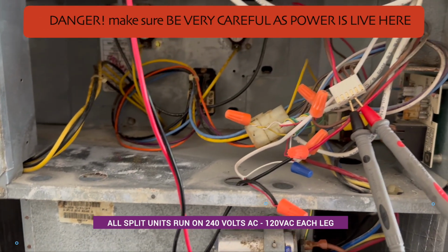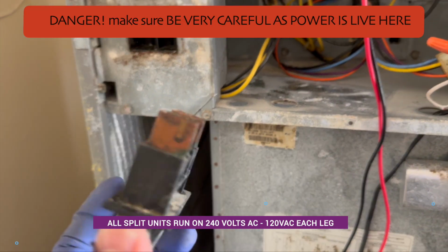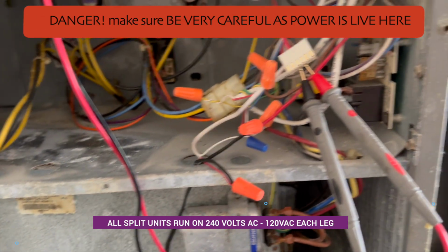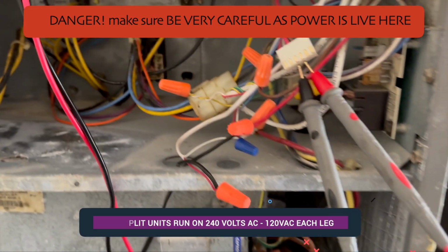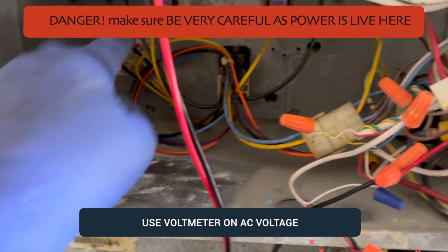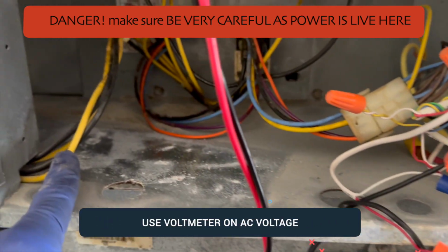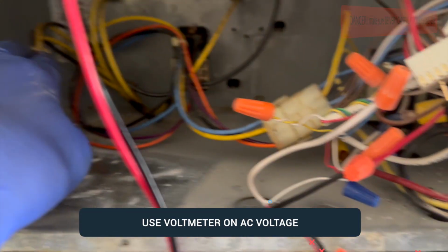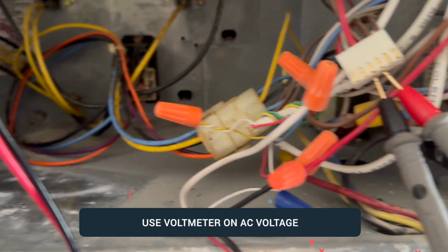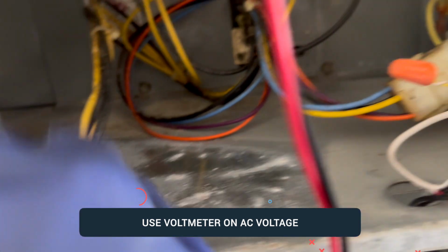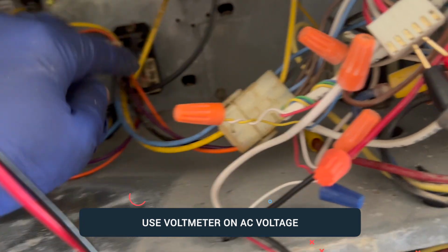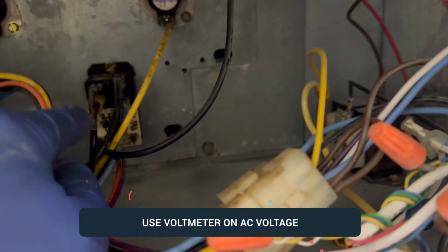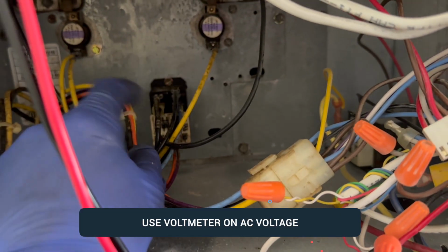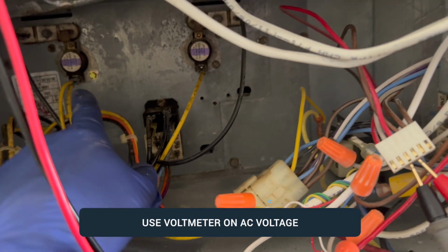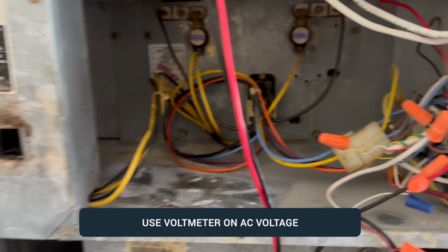Okay, I have the front cover off. This is my pull-out, already pulled. I have my meter set up, and the first thing you need to do is make sure you have voltage coming from here to this wire. You can test voltage on any of the black and yellow wires. I followed it, there's a yellow wire right here, a black one here, and I checked it, and I have 240 volts across here, so I know I'm getting proper voltage.